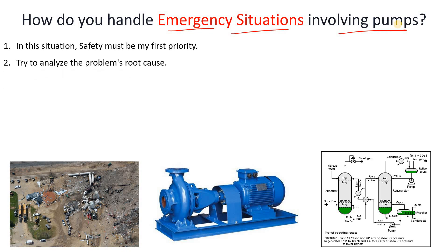Always try to analyze the problem's root cause. For example, if your pump motor's ampere is frequently increasing or decreasing, if the pump takes load and then drops it frequently, or if there is excessive vibration and noise within the pump — what could be the root cause?